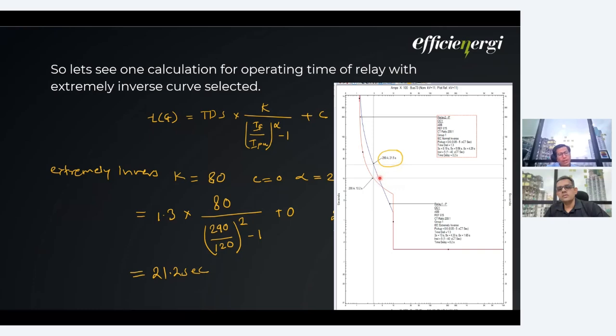The nature of this curve can be used where we are protecting equipment which has high inrush currents, or a high starting current or short-time maximum. Let's say we have a transformer. Normally you must have seen that for a transformer we generally go for extremely inverse characteristics, the reason being that the transformer has high inrush current. Again, the transformer has to carry the full load of the system. There is a possibility that for a shorter period there is a huge load requirement. Cold loading also can be higher at this stage. So we don't want to trip the system at a faster time. We want a delayed time.